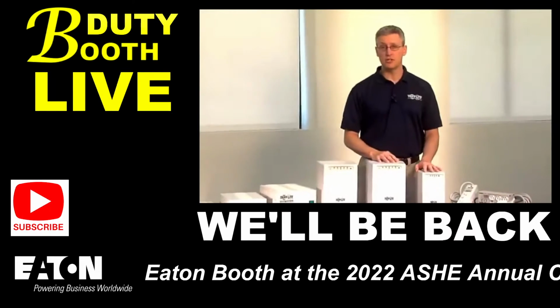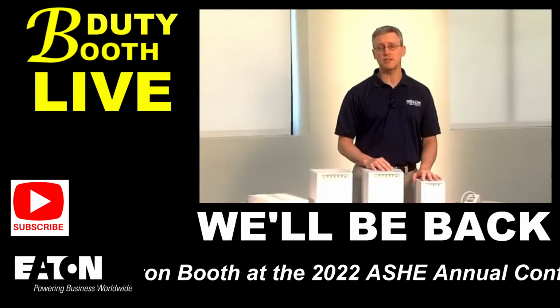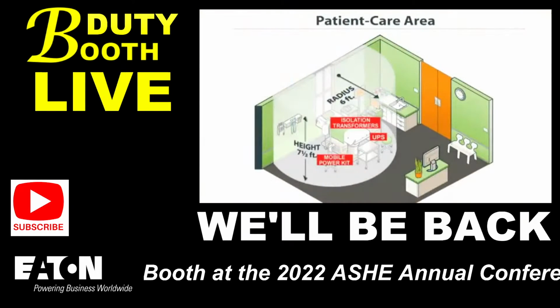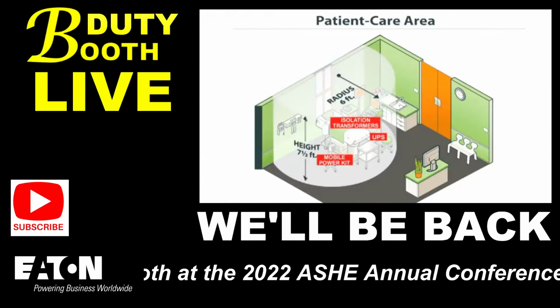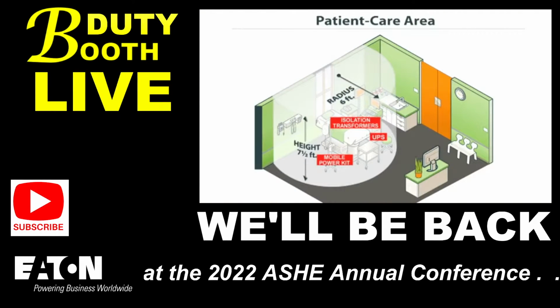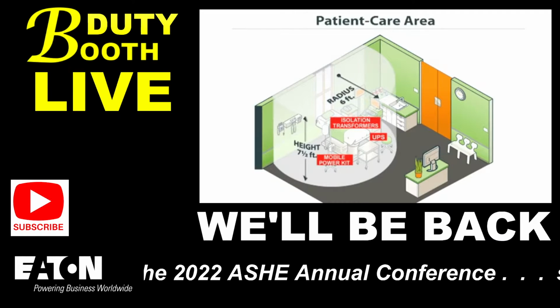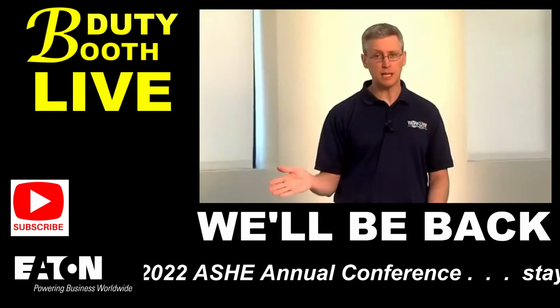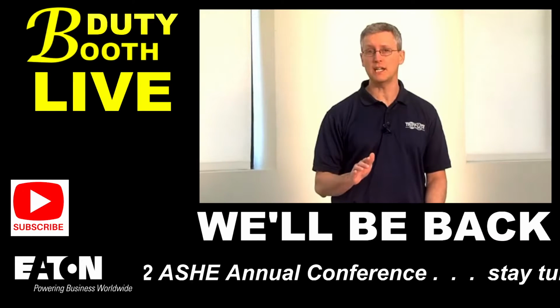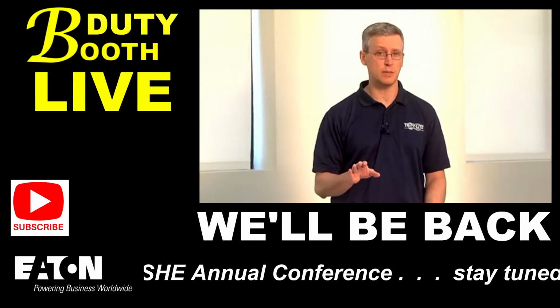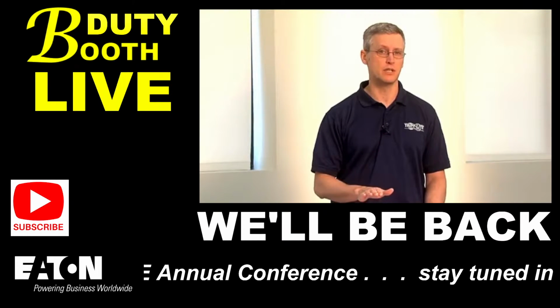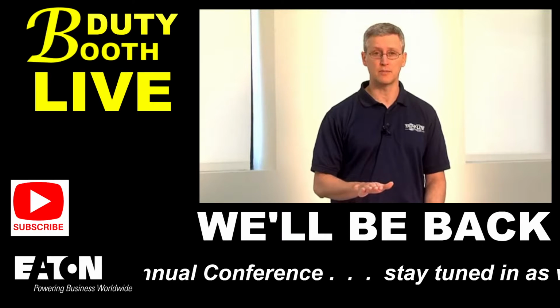Which Tripp Lite solution should you sell to healthcare applications? In patient care areas, sell Tripp Lite medical grade UPS systems, isolation transformers, or mobile power kits. All are compliant and reduce the combined leakage current of all connected equipment down to safe levels, under 100 microamps.